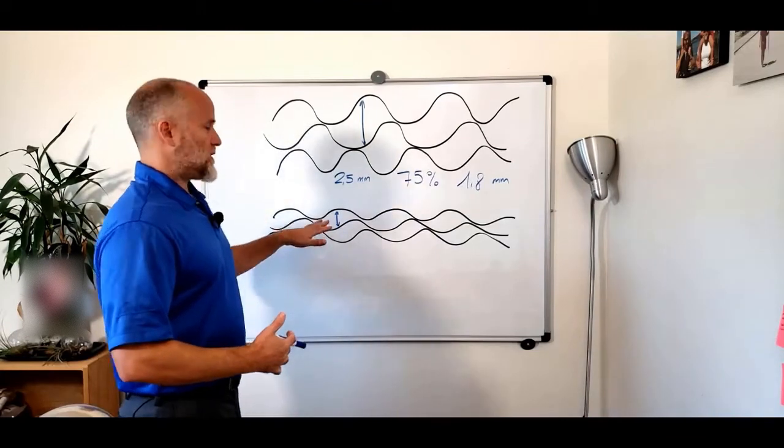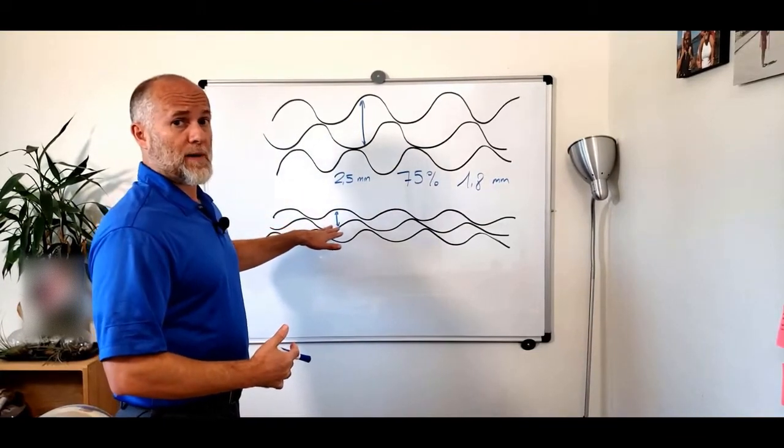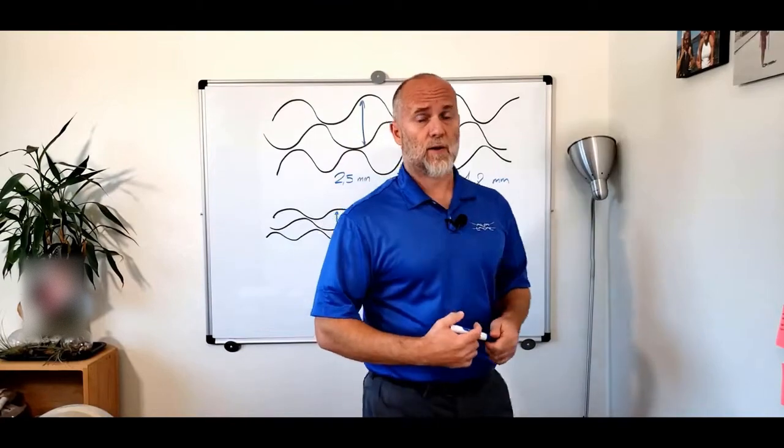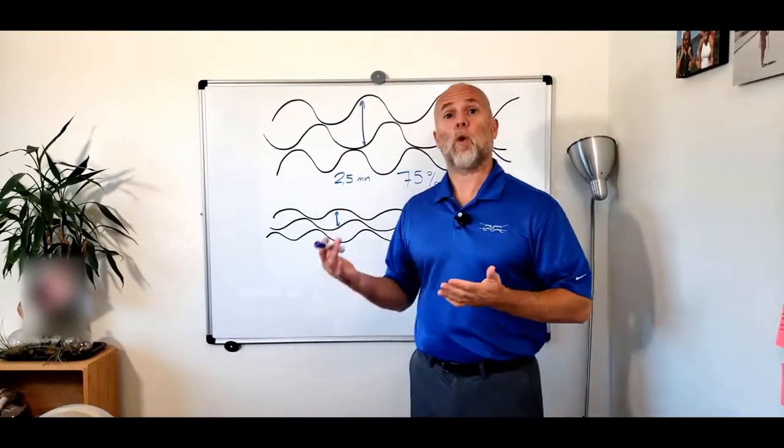Let's say that in this case, for instance, this is a 1.5 millimeter channel. You need to design your mesh in the strainer for particles that are around one millimeter.